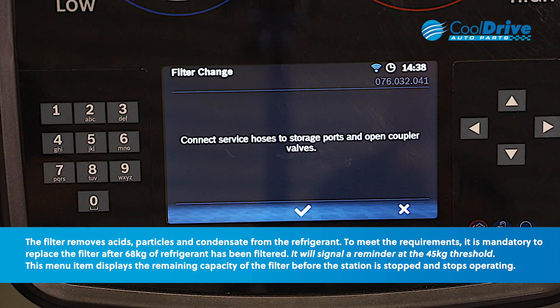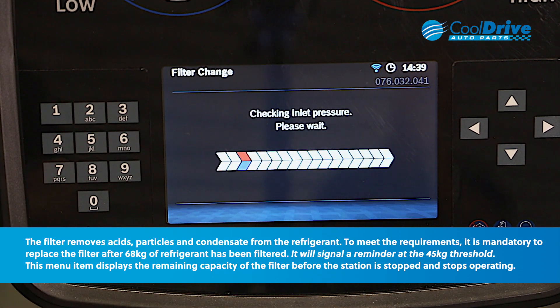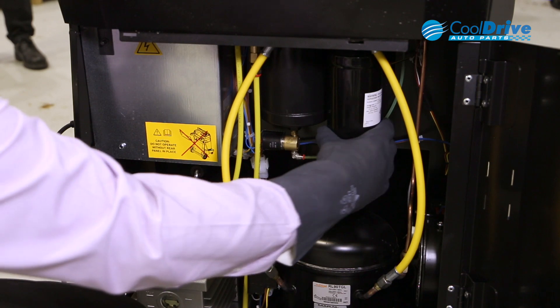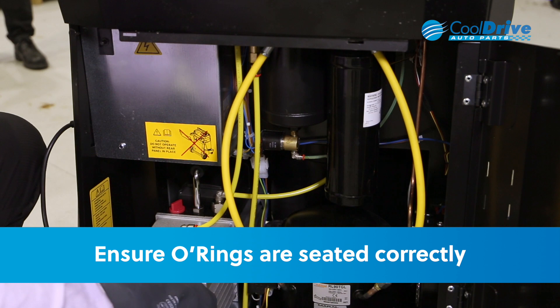We connect the service hoses to the storage ports and open coupler valves. This is to remove any refrigerant from the filter circuit. The filter assembly screws straight off and back on — just ensure the o-rings are seated correctly.